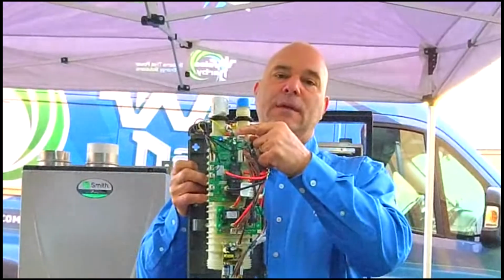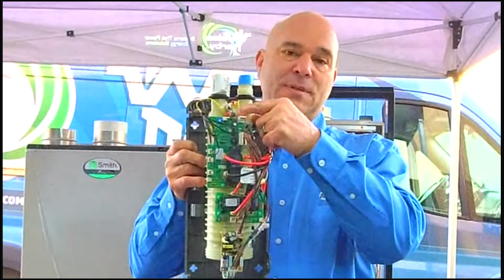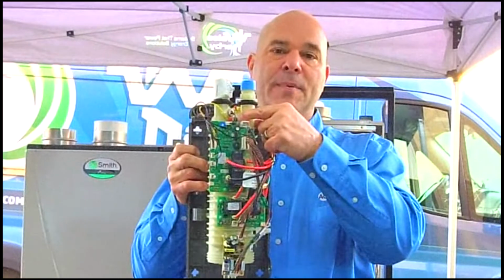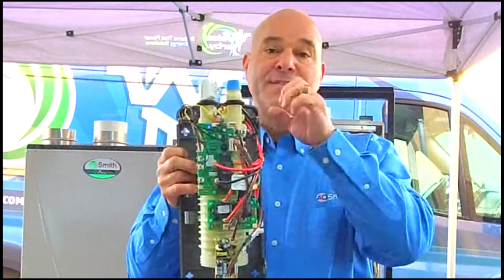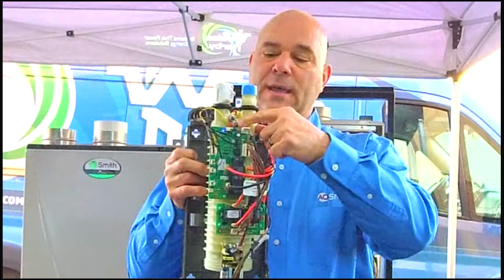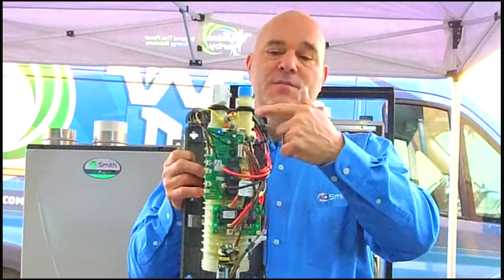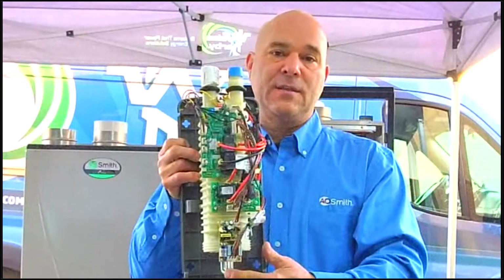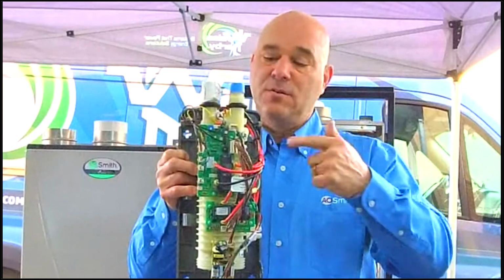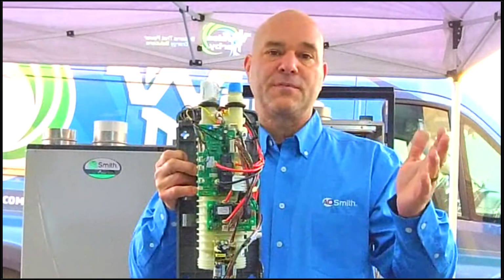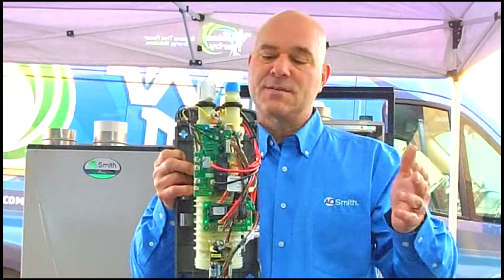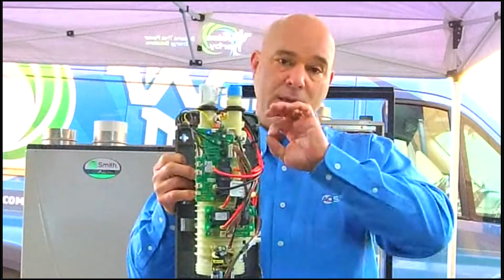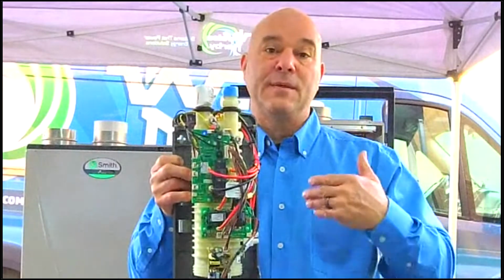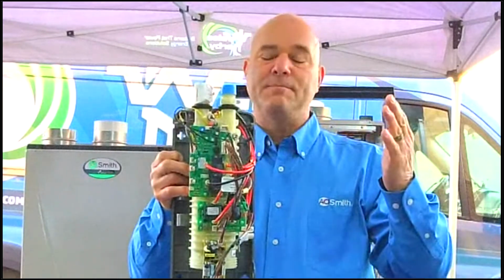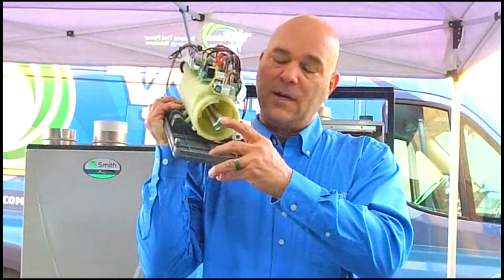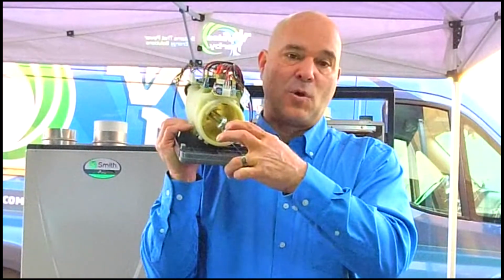Another real neat feature with our electric tankless is right here, this little brass screw. If you're in the boiler world and you deal with low water cutoffs, that's what this little brass screw does. This kills the element if it sees air, if it has a break in contact. So we're getting basically a ground signal to the water. It says there's water, the chamber's full of water. We're not going to dry fire the element, and that allows us to protect that heating element. That's what fails in tankless electric, the heating elements, because you'll get an air bubble that goes across them and the temperature on them is pretty hot and they'll pop. So main reason we go with this type of element, it's more robust.